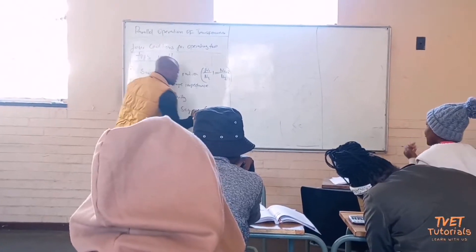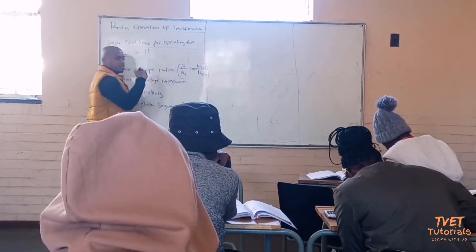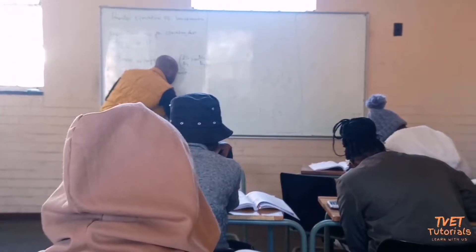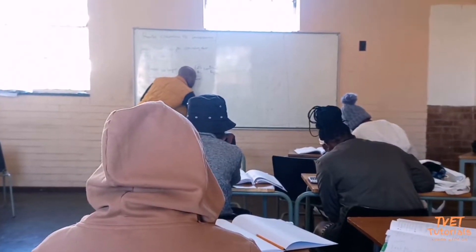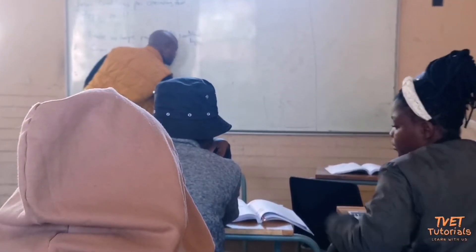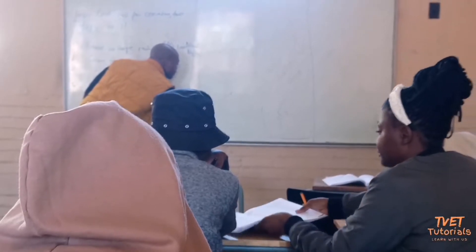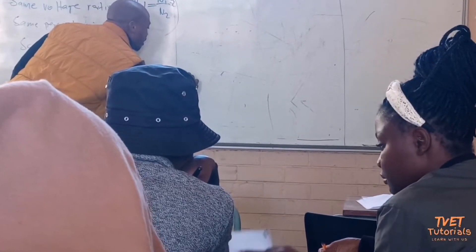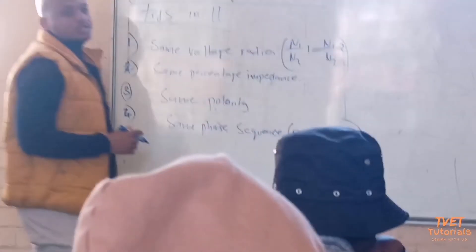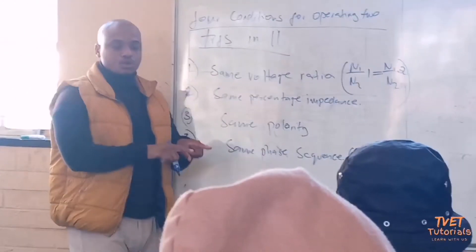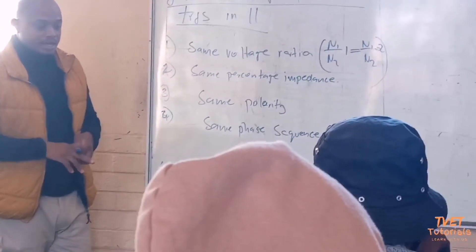What I mean by that is: if one transformer has a phase sequence of R, Y, B, it means the other transformer must have the same sequence of R, Y, B. Those are the four conditions that need to be met when we operate two transformers in parallel.